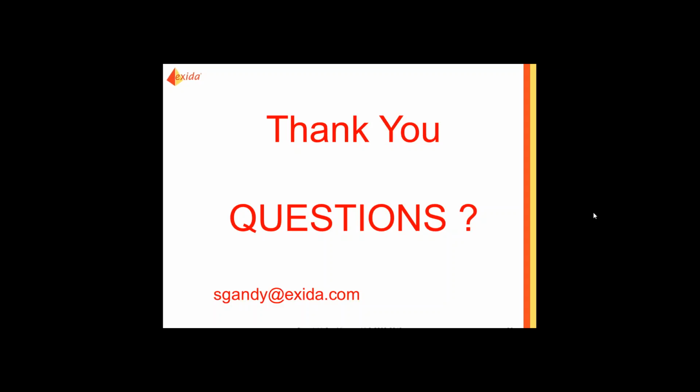What else do we have here? In the new 61511, who is responsible for the SRS review and the FSA? Is this the end user, EPC, or more towards the system integrator now? Well, the standard is very clear that you need to show independence, and so therefore you could use a third-party company like exida to do that because that's fully independent. What they mean by that is you need to use somebody that's, number one, competent, and secondly, is not associated with the design in any way. So again, those are the two requirements, and the new 61511 is going to put a lot more emphasis on competency. And in fact, I've been told there's a lot more shalls in it than there was in the other one.